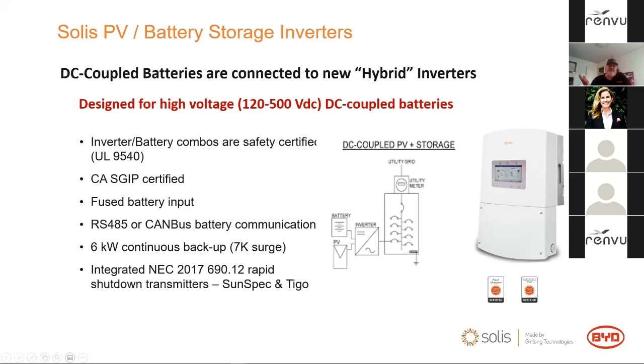So when you set up one of these systems, you really just have the inverter itself. It does battery management, it does the PV. You can set up these systems, as you saw, we have 5, 7.6, and 10 kilowatt inverters, and those really all output the same 6,000 watts. These inverters are ideally set up for systems with short duration power outages, TOU, and self-consumption of all the solar kilowatt hours you collect during the day.